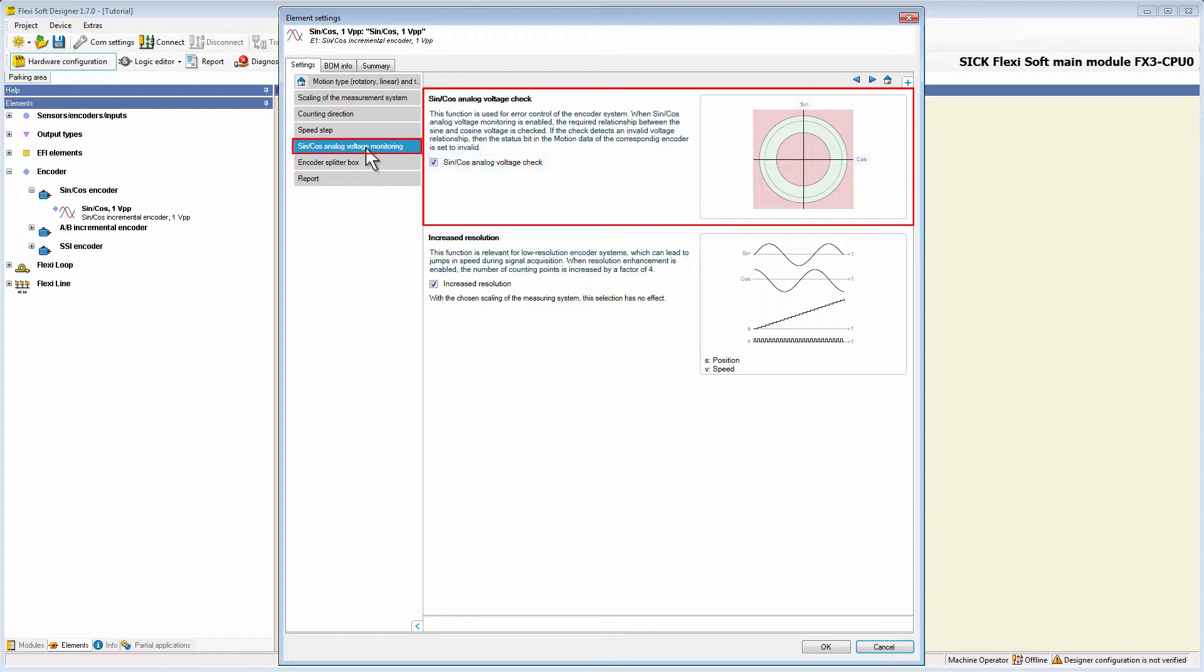If the parameter is not enabled, performance level D cannot be reached with a single sine cos encoder.